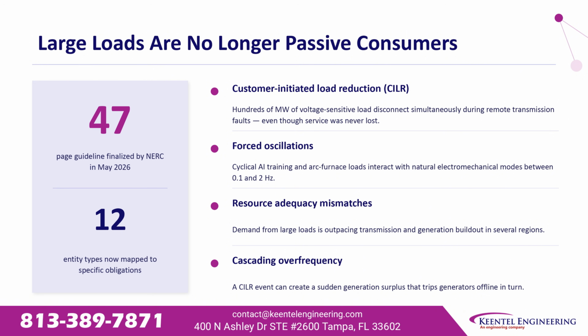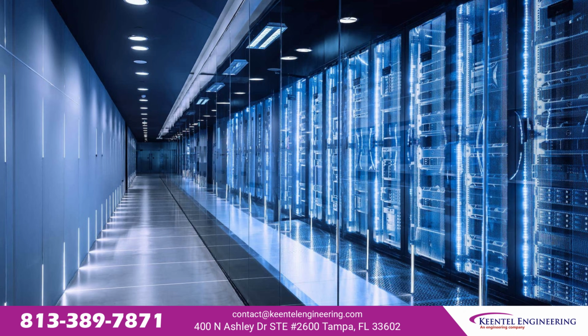Forced oscillations, where cyclical AI training and arc furnace loads interact with natural electromechanical modes between 0.1 and 2 Hz. Resource adequacy mismatches, where demand is outpacing transmission and generation build-out. And cascading over frequency, where a load reduction event creates a sudden generation surplus that trips generators offline in turn.